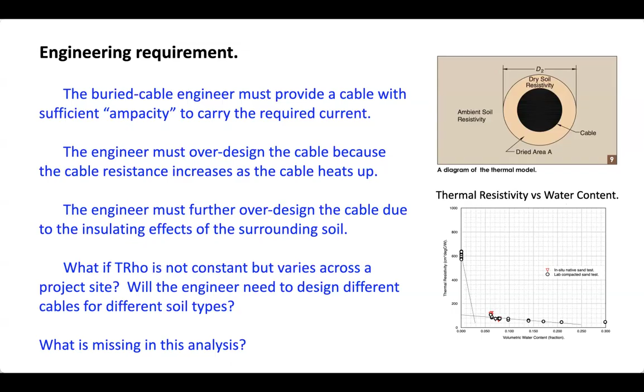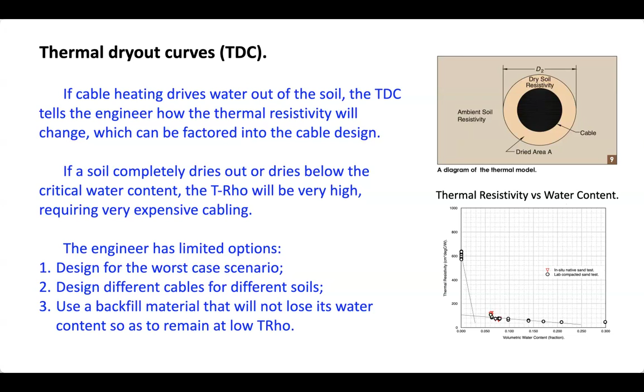The dynamics, as I visualize it, is that cable heating drives water out of the soil. The thermal dryout curve, which I guess I should have described, tells the engineer how much thermal resistivity will change, which can be factored into the cable design. If the soil completely dries out or gets below the critical water content, the thermal resistivity will be very high, requiring very expensive cabling. So the engineer has limited options: design for the worst case scenario, design different cables for different soils, which is also very expensive, or use a backfill material that will not lose its water content so as to remain with a low T-rho. So the thermal dryout test is not a field test, it's a lab test.